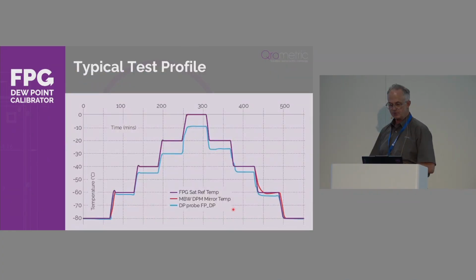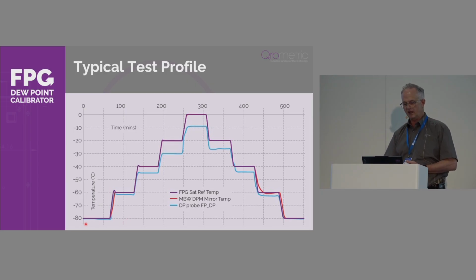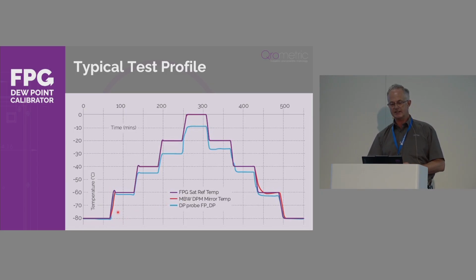In this case, we have a sensor, a dew point mirror, and the FPG saturator temperature all plotted at the same time. You can see that at -80, the sensor has been adjusted at -80, so it agrees very well. Then we go to -60, you start to see some deviation. At -40, it's a little bit worse. And as you get to the higher range, you've got a 10 degrees difference.